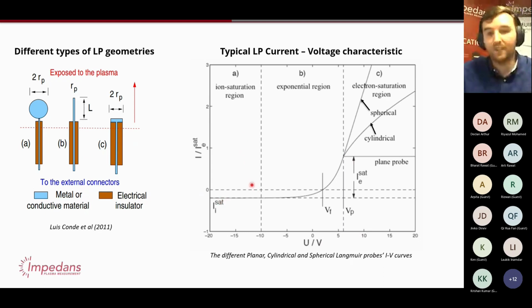When the voltage is sufficiently negative, you're only collecting ions. So that's giving you information about the ion density. When it's sufficiently positive, you're collecting electrons and repelling ions. So that's giving you information about the electron density. And then there's a region in between, and that gives you information about the electron energy distribution function. So how many, and what the energy profile is of the electrons in the chamber. We'll go into this in a lot more depth in a couple of slides.